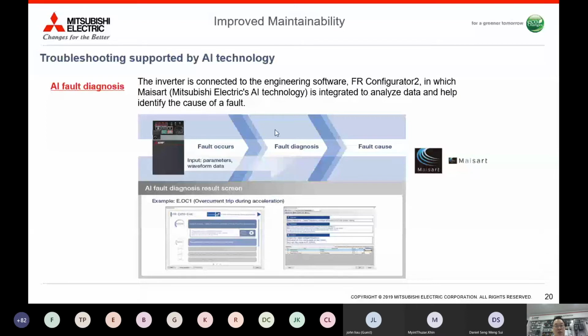When the drive trips, a fault occurs, you'll see the error code, and the system allows you to take corrective action, knowing the cause of the fault. For example, this screen shows EOC1, which is overcurrent during acceleration. You can see when the fault occurred, and the fault diagnosis function lets users troubleshoot more easily. These functions are very useful for people in the field, even without special skills, which contributes to reducing severe downtime.